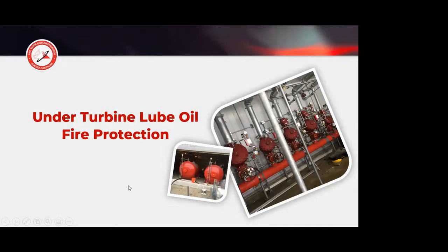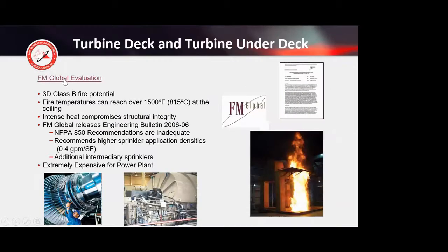These are some projects that we've done in the field. This goes back and talks about an FM Global study that was done back in 2006. I'm sure that if I click on that, the hyperlink doesn't work, but basically they put in their calorimeter in Providence, Rhode Island, tested an under turbine lube oil spray fire. And what came out of that test was that the fire's temperatures reached over 1,500 degrees at the ceiling, and that was a high enough temperature that could compromise the structural integrity of the steel. So they were like, oh, that's a bad deal.